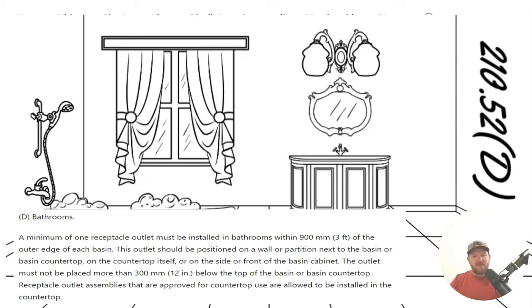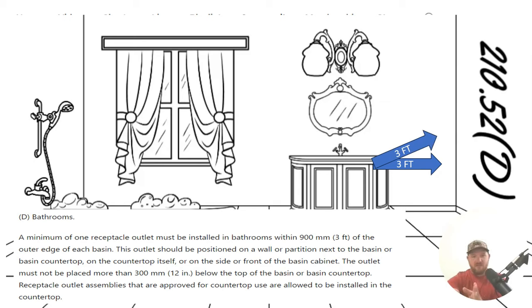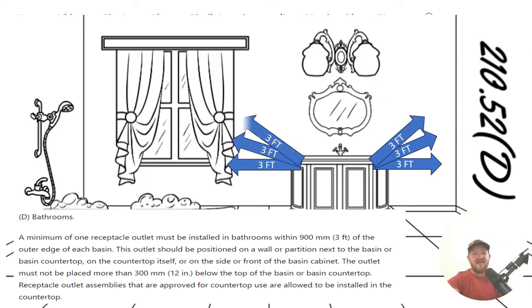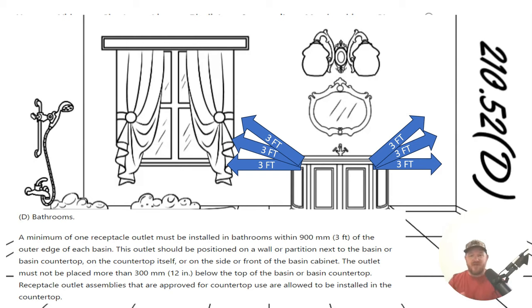Now, let's stop right there and then we'll finish reading it here in just a moment. What this is saying is within three foot of the edge of that basin, I'm imagining that somewhere on this vanity, the basin starts here. And you can just continue, whether you're on the left or right side, anywhere in that three foot zone and you could draw an arch across it. Anywhere in that zone, that receptacle is allowed to be placed.